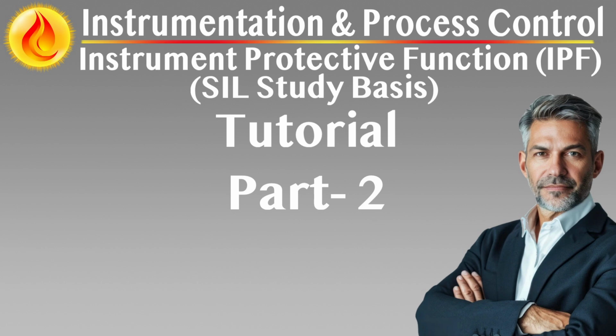Process safety time, PST, is the maximum allowable time between the initiation of a hazardous process deviation and the point at which unacceptable consequences will occur. It defines the response window available for an Instrument Protective Function (IPF) to detect, decide, and act, making it a critical factor in both SIL assignment and system design.